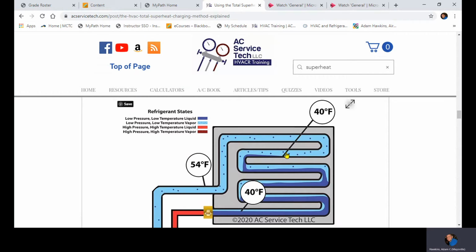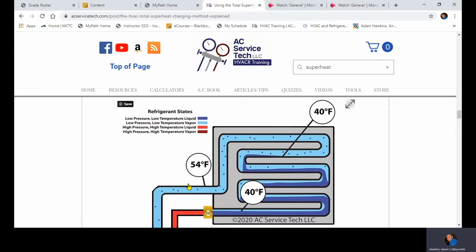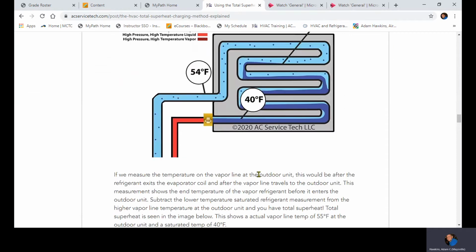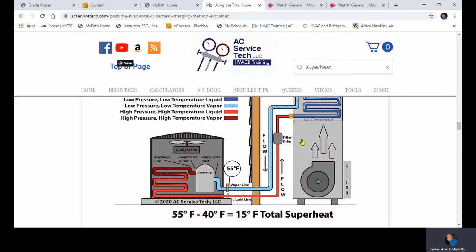All right, so I mentioned earlier that your saturation temps aren't going to change during the part where it's changing states. This is kind of proof of that. If you could measure pressure entering the evaporator, which you really can't, and leaving the evaporator at the saturation point, it would be the same. So that whole low side is going to be under the same amount of pressure. So this 14 degrees extra of superheat, you don't see that on your gauges. That is sensible heat, not latent. Your saturation temp is measuring kind of the latent. I know it's confusing.